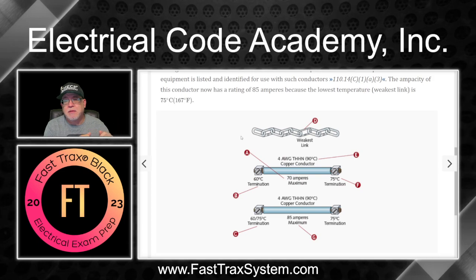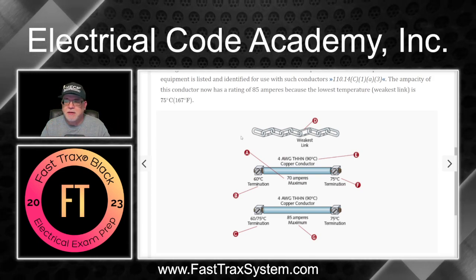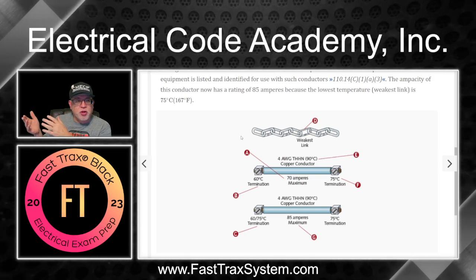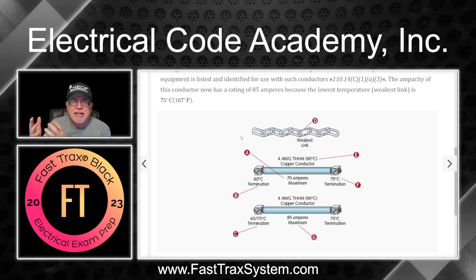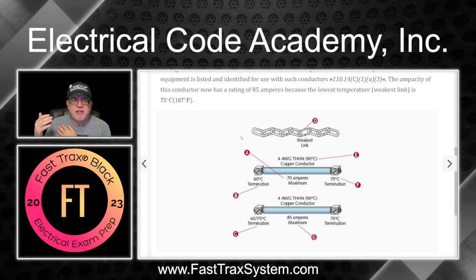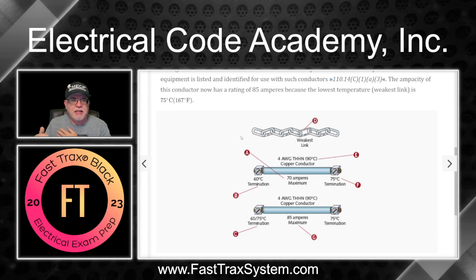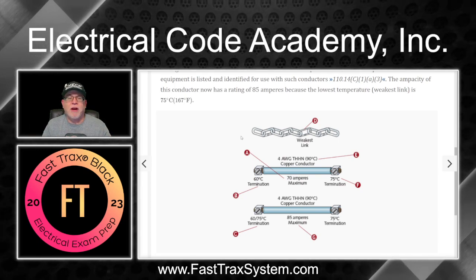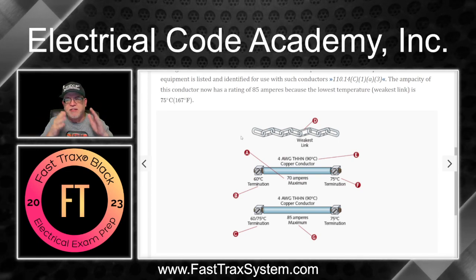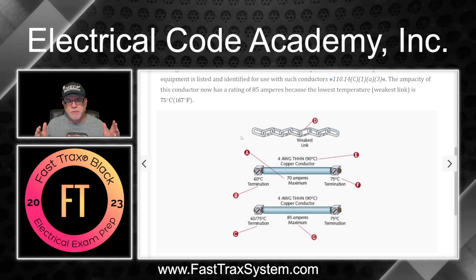Terminals have a rating, wire has a temperature rating, and then ultimately whatever you're terminating onto has a rating, whether it's 75 degree C rated lugs or 60 degree or even 90. So everything has a rating. So think of it as three pieces, if you will.